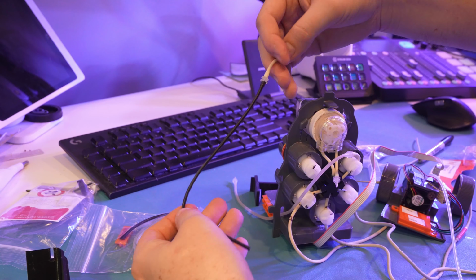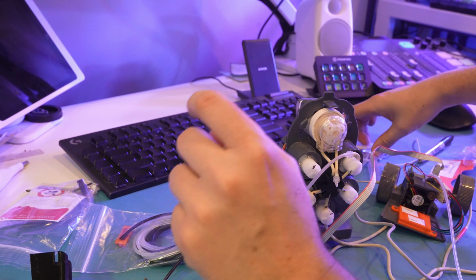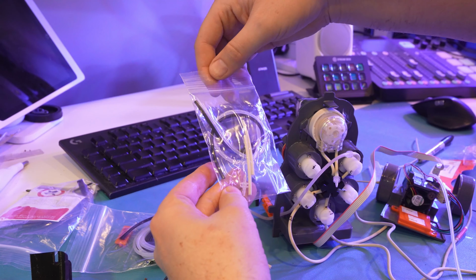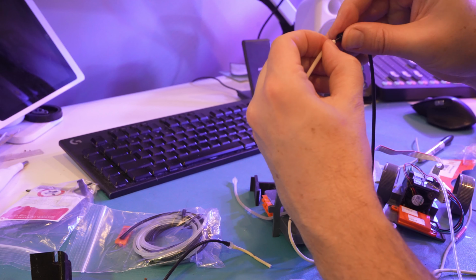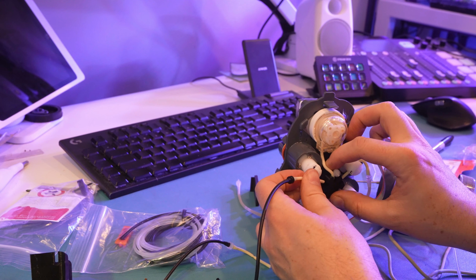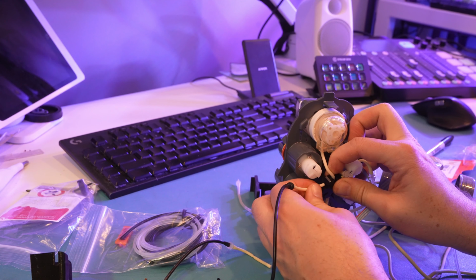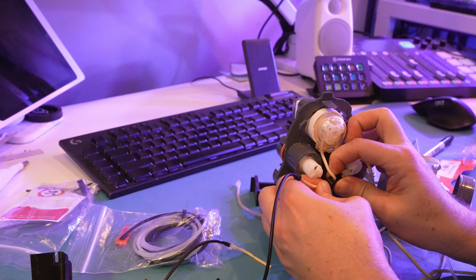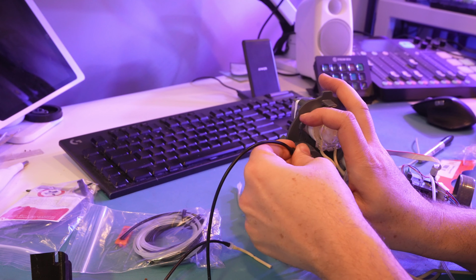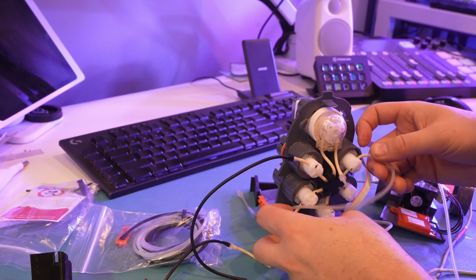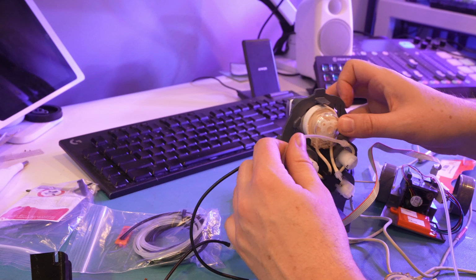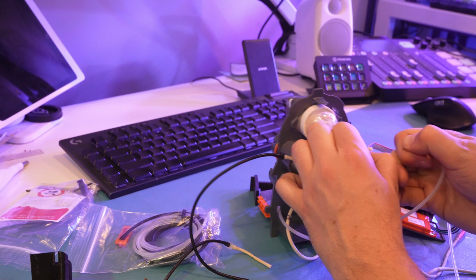And look at this one, we got our black line to our little piece of tubing. And we got a similar thing in the new kit. Now, just to make my life easier, I'm gonna put this on the manifold and then I'll push it through the solenoid. And to get these back in, all you do is kind of push and slide them in, so it's pretty easy.